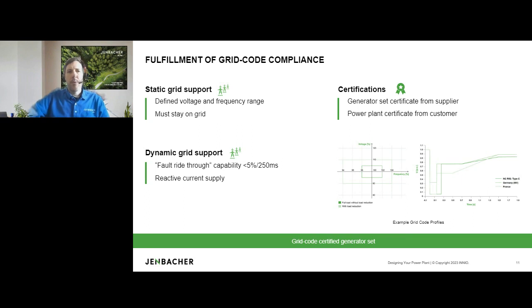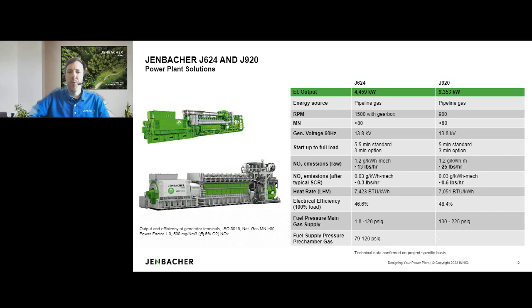We also know that grid code compliance is becoming more important as these units are used to support the grid. So there's static grid support, where a defined voltage and frequency range is set and the units will stay on the grid throughout that range. There's also dynamic grid support, which is a fault ride-through capability and reactive current supply. And we also offer certifications for those. So we're seeing more and more of that in the requests we're handling, as customers are asking for these types of solutions.